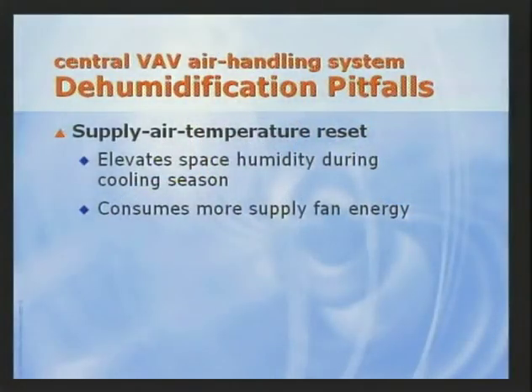Now, by continuing to supply cool, dry air at part load, VAV systems typically provide effective dehumidification over a wide range of conditions. However, two issues that can pose a dehumidification challenge to a VAV system are the use of supply air temperature reset and high minimum airflow settings at the VAV terminals. In many VAV systems, the supply air temperature is reset upward at part load conditions in an attempt to save cooling or reheat energy. However, this warmer supply air results in less dehumidification at the coil and elevated space humidity levels.